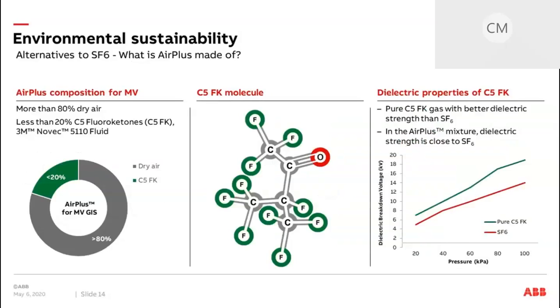AirPlus is a gas that has been developed together with 3M, which consists of C5 fluoroketones. It's a mixture we use in the switchgear that consists of roughly 80% dry air and 20% C5 fluoroketones. And C5 itself has an even higher dielectric strength than SF6, as you can see on the right side. In the mixture we use, it has a comparable electrical behavior.